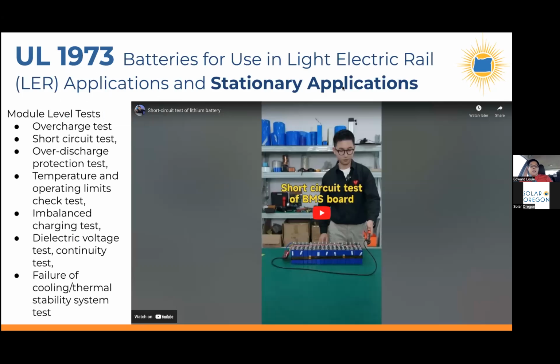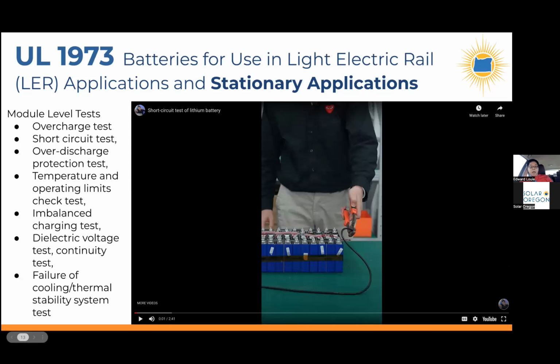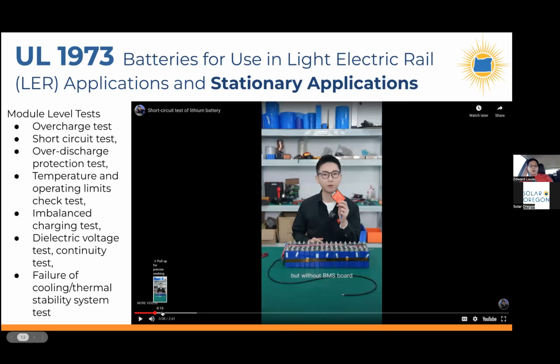So this one is at the module level. It's a very similar array of testing: overcharging, short circuit. And for example, this guy here is showing him dead shorting a pack of lithium iron phosphate cells. The reason he's more than happy to stand right next to the cell and dead short it is because there is a working BMS that's protecting the cells, and therefore when you use a dead short, it's able to disconnect the batteries to prevent a thermal runaway.